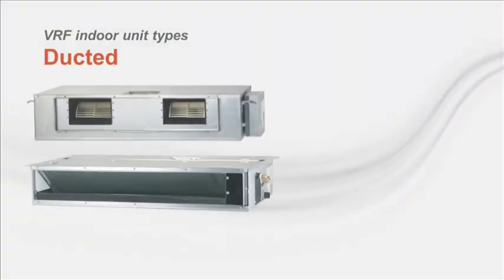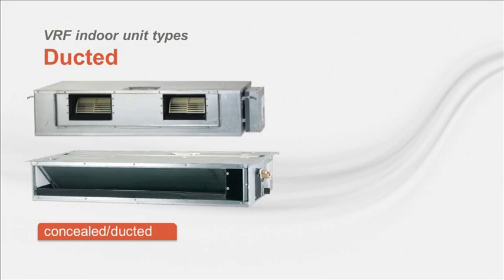Short duct runs can be connected to the supply side of indoor units located throughout a building, allowing them to distribute air to larger zones or multiple rooms. For example, there are a number of designs of concealed indoor units that look much like conventional fan coils. They are intended to be concealed in ceiling spaces or soffits. One common style is often called slim duct due to its low height profile, often 8 inches or less, making them suitable for hotel rooms and assisted living facilities.